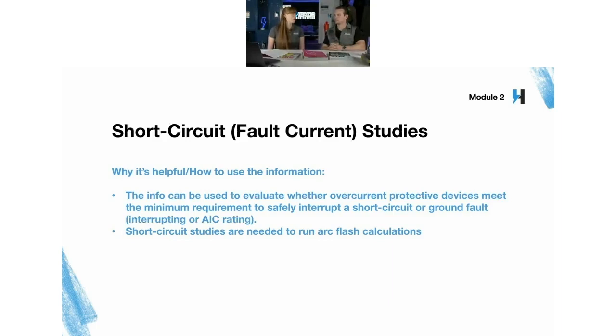Yep. So the rating of the device must meet or exceed the available fault current of the system. And that's kind of a big deal. If you don't really know what that means, it sounds kind of confusing, but it's a huge deal, because what happens if you don't have the proper rating? What if it's way underrated to the available fault current in the system? So essentially you want your overcurrent protective device to operate safely at the available fault current in the event there is a fault on the system. If the device is rated lower than what's available in the system, it might operate unsafely, or in other words, there could be an electrical explosion. Right. So it's very important to have this data. It's not a nice to have. It's highly important, because if something were to happen, you want your devices to clear the fault rather than exploding because of the fault. Yep.